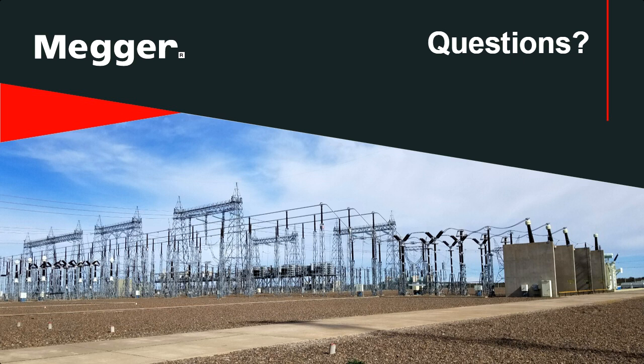So Doble is just a power factor test, right? You're just looking at watts loss or leakage current or capacitance. Depending on who you talk to, some people don't find it useful. You don't get a lot of information on SF6 breakers. You get more information on your OCBs, your oil circuit breakers. So this is still a fine test to run. On those, you usually run about 6 tests, all open tests. Back in my day when I first started, we had 9 tests, so you tested all 3 closed as well.